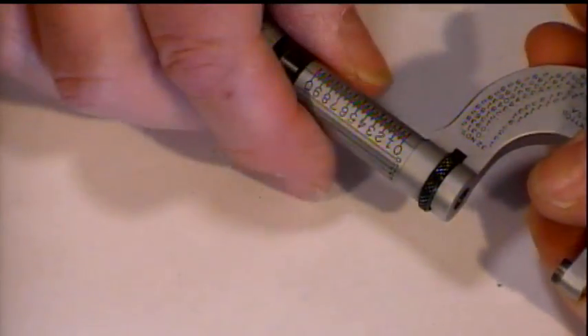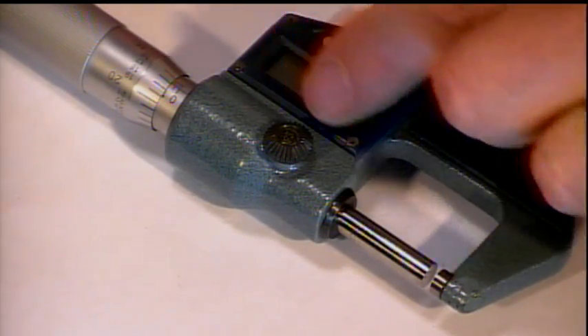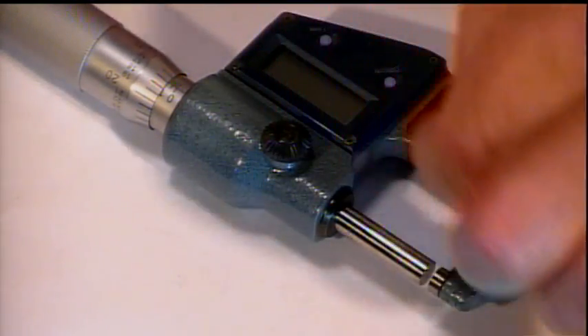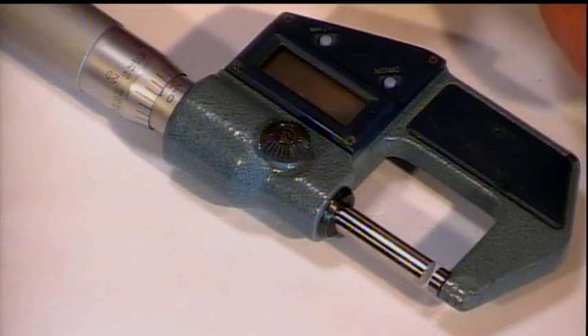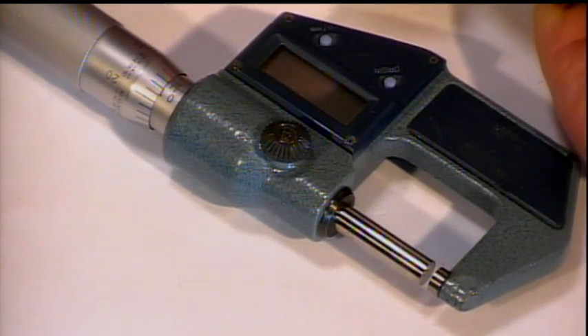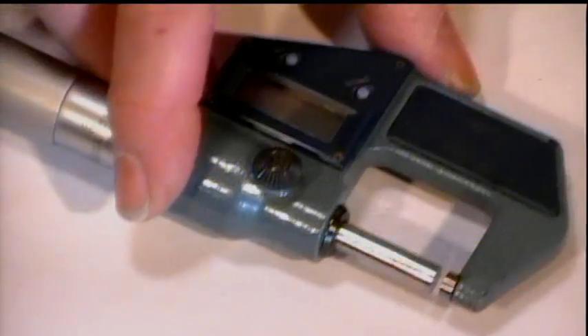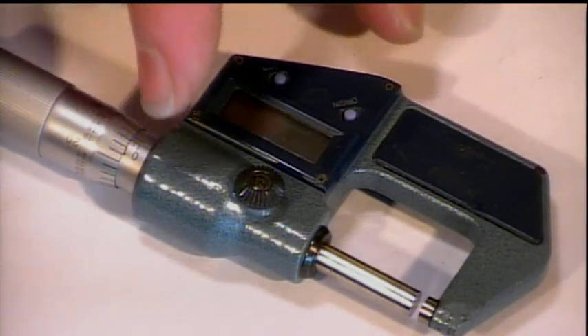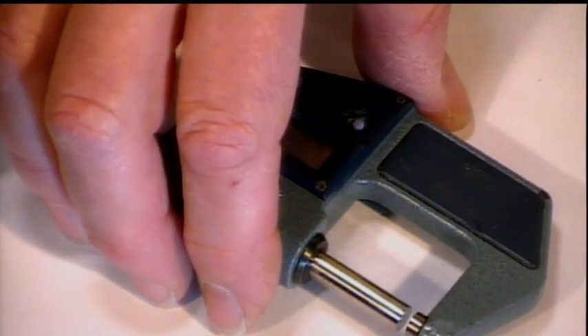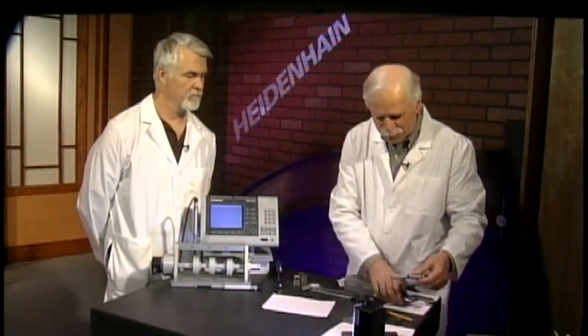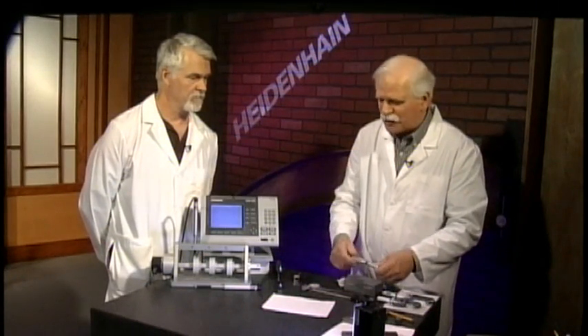Okay. You do. Now, this adjusting the split nut will not work on digital. The digital micrometers, inside there's actually a groove and a screw riding on them. The back end does not come off. You're going to break the micrometer if you try to open them up. If a digital micrometer ends up being too loose, it's going to need to go to the calibration lab. We have ways to adjust it, but it's beyond the scope of this program. We wouldn't suggest you open them up.